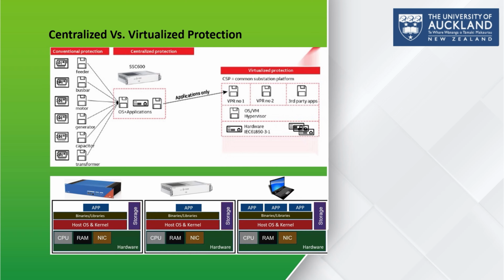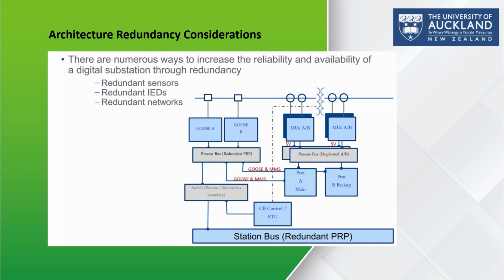Architecture redundancy considerations. A digital substation improves reliability and availability by using multiple layers of redundancy. This diagram shows how this redundancy is introduced at different levels of the system. First, redundant sensors and redundant merging units ensure that voltage and current measurements continue even if one sensor or merging unit fails. These merging units publish sample values on two separate process buses, providing duplicated measurement data paths.